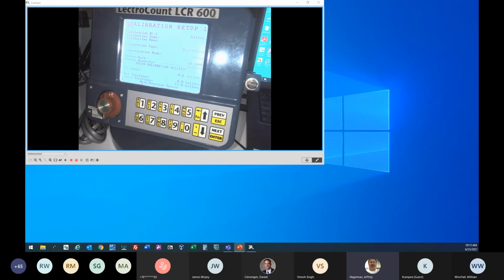You're really just entering in what the prover quantity says, whatever the figured prover quantity or master meter volume was that went through the meter. You're just telling that information into the register, and it's doing all those calculations that Tom was showing in his presentation. It's doing that all for you. Exactly. Yeah, it's doing all the background math for you. So all you've got to do is worry about putting in the correct prover quantity, and that's really all you need to do. Right. All right.